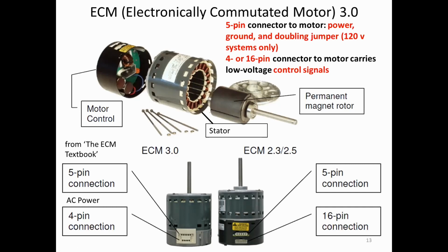This is an ECM3, which I again have in my furnace, a Regal Beloit ECM3, and that's why I'm particularly interested in it. The ECM3 has a fixed frequency 18 kilohertz pulse width modulator, and I'm going to show you what pulse width modulation is in a minute. And it varies the phase switching speed from about 300 RPM to 1200 RPM, although there are some motors that can run up to 1800 RPM. For those of you that are familiar with motor theory, the legacy motors have 18 poles. The newer sine drive motors that Regal produces have 12 poles. Now let's talk about how this works, and then we'll talk about mitigation.